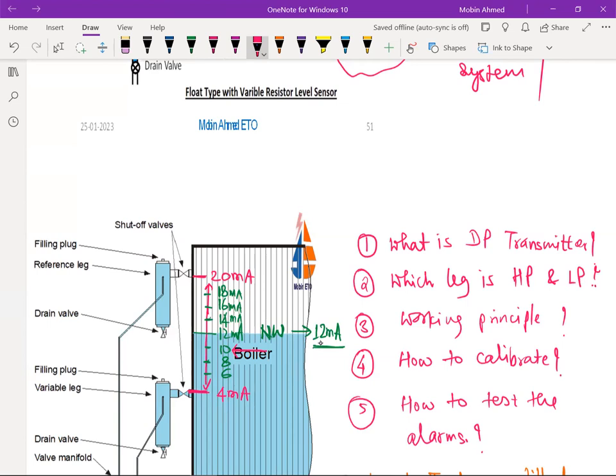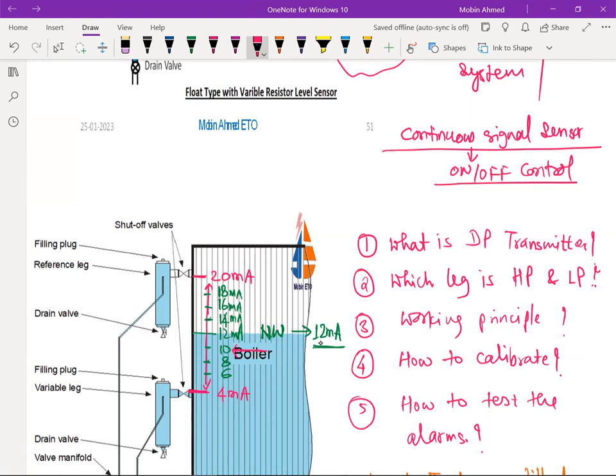one thing you should remember is that we are getting a continuous signal from the sensors we have. This can also be used for on-off control. Remember, we can use this as an on-off control, like we are using here. It is very much used for continuous control, but it can also be used for on-off control. So suppose we use it for on-off control, then at the 10 we are going to start the pump, then at the 14 we are going to stop the pump. This is just an example I'm quoting here. It will work like this if it is a start and stop.